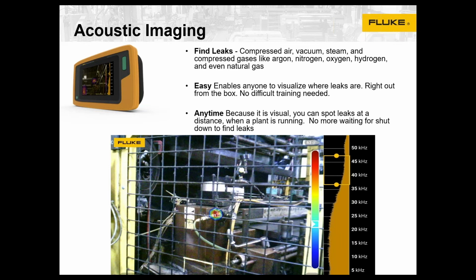Acoustic imaging is easy, enabling anyone to visualize where leaks are very quickly, right out of the box, with no extensive training or experience needed. You can use it anytime because it's visual. You can spot leaks at a distance, that's the detection part, when a plant is up and running. So you don't have to wait until the weekend or downtime to have somebody walk around and listen for leaks using older methods such as soap and water based on listening. No more waiting for shutdowns.